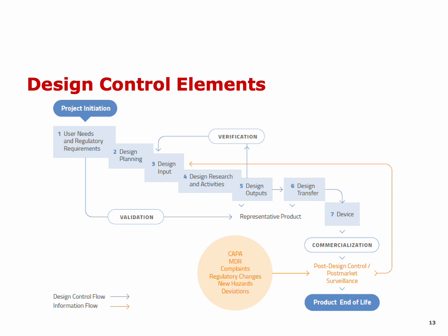Then we are going to go through another point, which is the design transfer. Why? That's because when we are doing our research, this is like research and development labs, we look into the design as well. Once the design is well established, we are now going to write different documentation related to even how to make those devices, including the software if applicable. And then we will need to transfer that from research and development labs into a manufacturing facility where we'll be able to upscale the production.